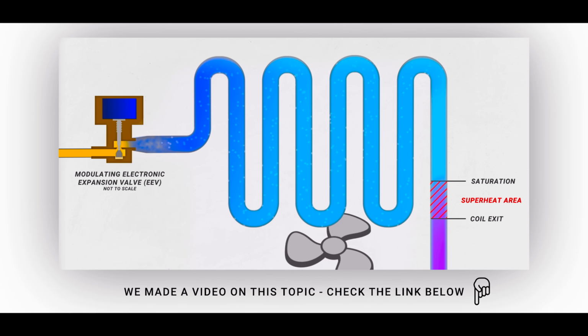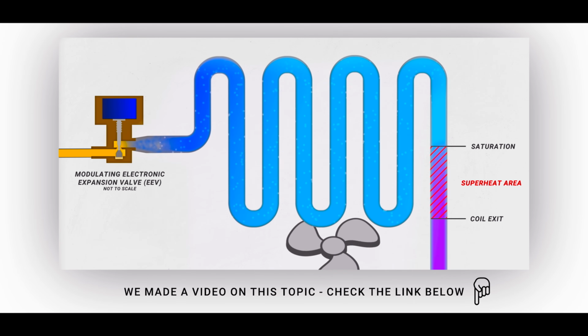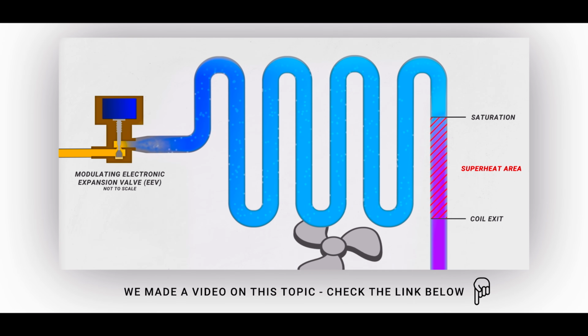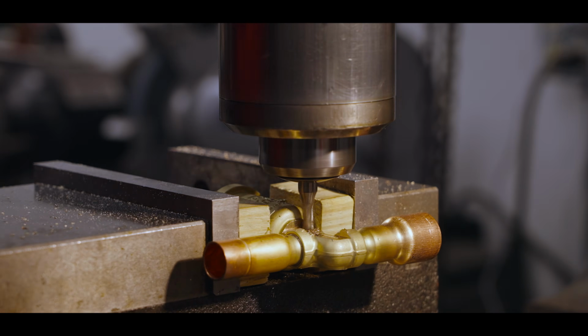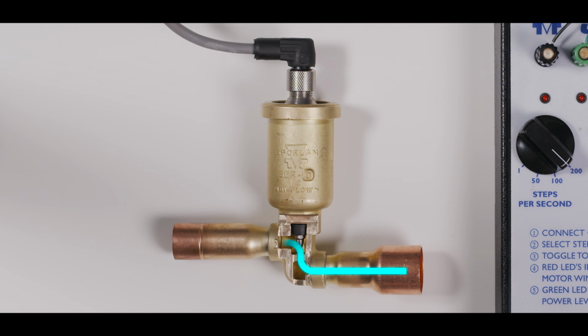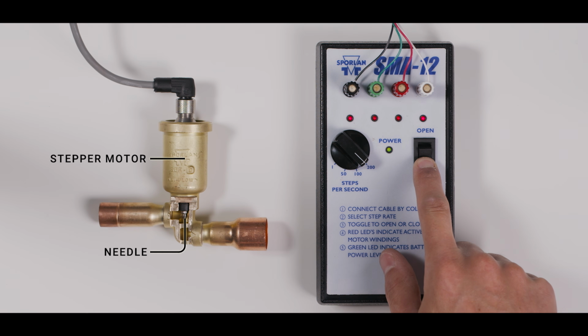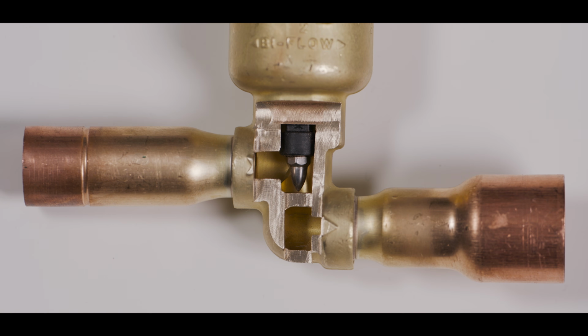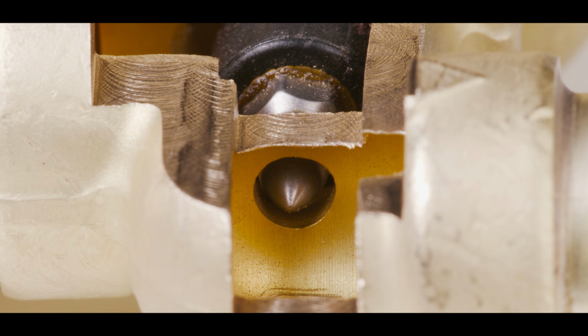Since the EEV is responsible for controlling superheat, this is one of the biggest safeguards in ensuring the compressor isn't exposed to liquid refrigerant. So let's cut into one so we can see how it works. The refrigerant flows in this direction and is metered by this needle. Moving the needle is a stepper motor. When we close the needle, it changes how much refrigerant flows through this orifice.